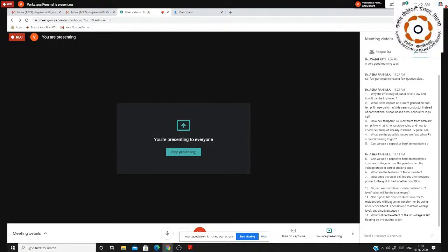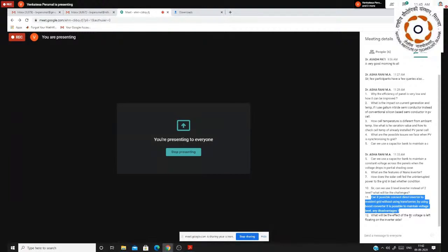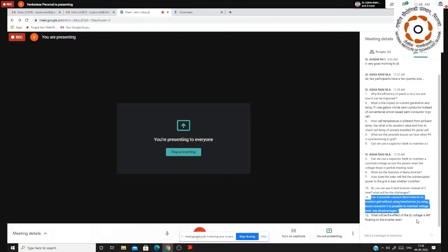Is it possible to connect the inverter directly to the residential grid without using a transformer? Any disadvantage? By using the boost converter, it's possible to maintain the voltage level without a transformer. If the boost converter is able to support the DC bus at the worst condition, you can do it; otherwise you have to use an isolated topology, a high frequency transformer at the DC bus side. There's no harm in using the boost converter followed by the inverter connecting to the grid, but the condition is that the boost converter should not be stressed out.